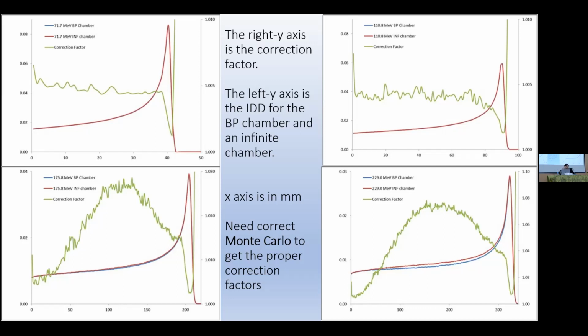Again, the reason this is important is because when you put this into the treatment planning system, the first part is you don't know exactly what's coming out of the machine, right? Something's coming out. That something is going to be a spread in positions, this spot size. It's also going to be a spread in energy. Synchrotrons can sometimes pull out really tight energy. So when I say 70 MeV, it's going to be 70 MeV plus or minus like 0.5%, really tight. A cyclotron is going to be a little bit wider. We talked about that earlier because of energy degradation and such, but this might be a percent or two. That's going to have a different influence, since you lose 1% per centimeter as you're going through all these different things. These are going to look a little bit different depending on the machine you're using. Although they're going to be similar, it may be a 5% difference, 6% difference, or maybe 3% difference, depending on the exact characteristics of your system.